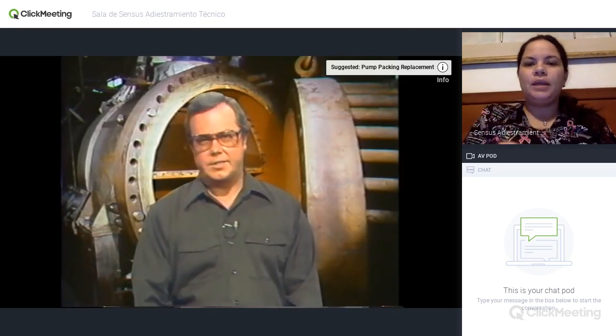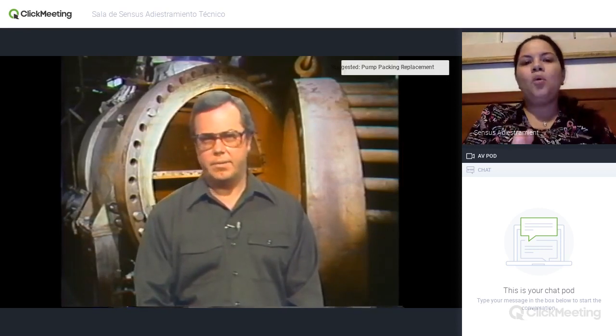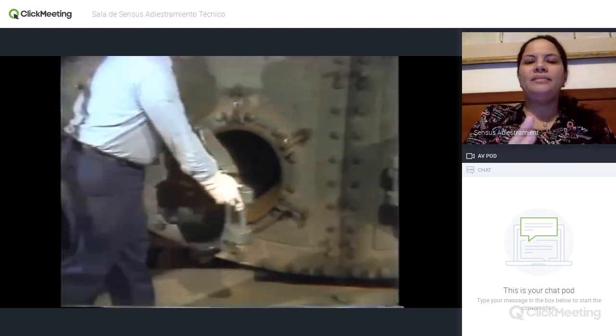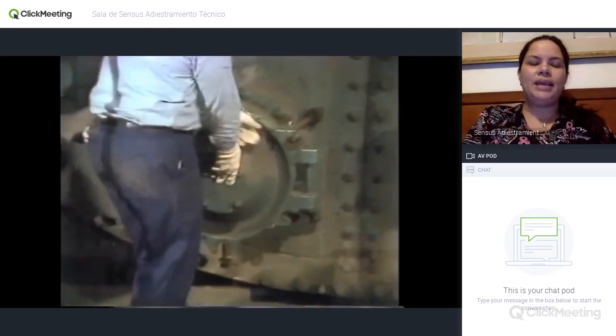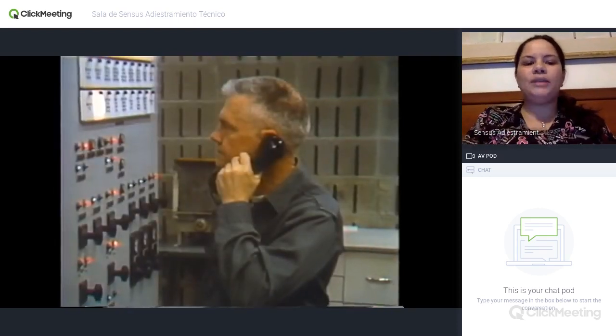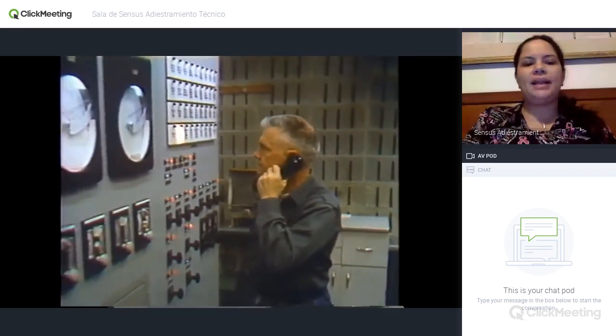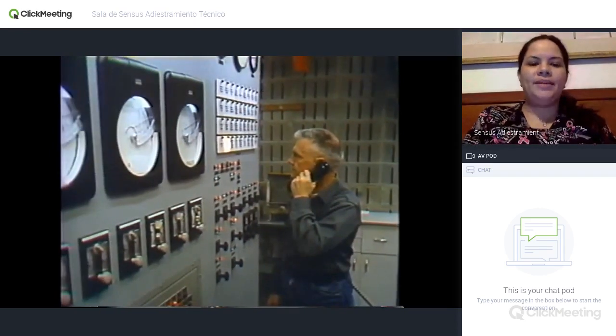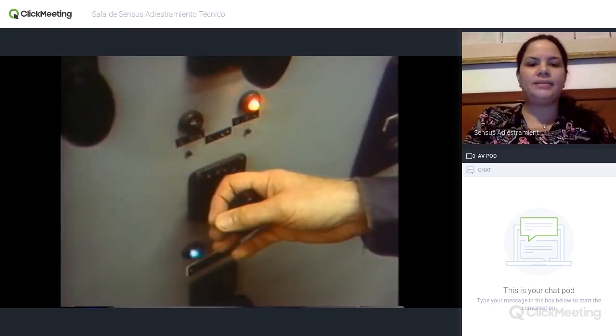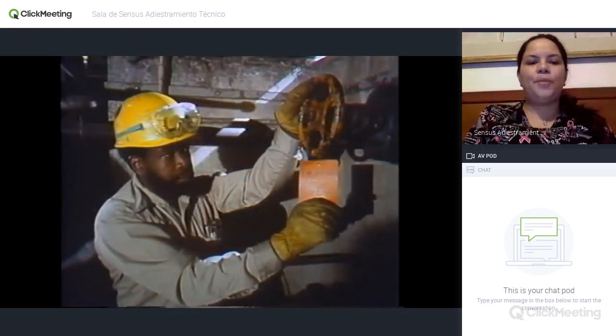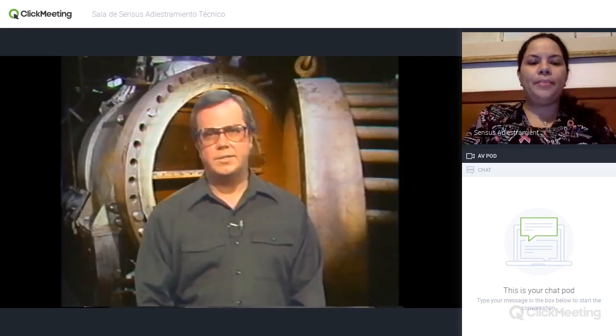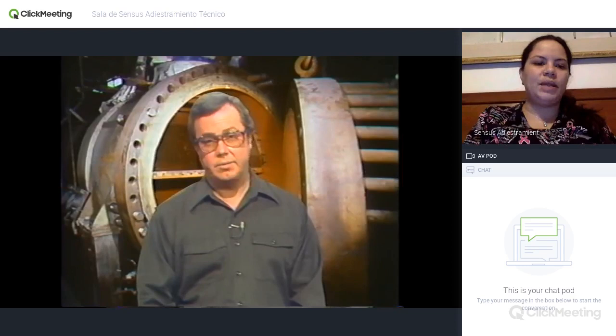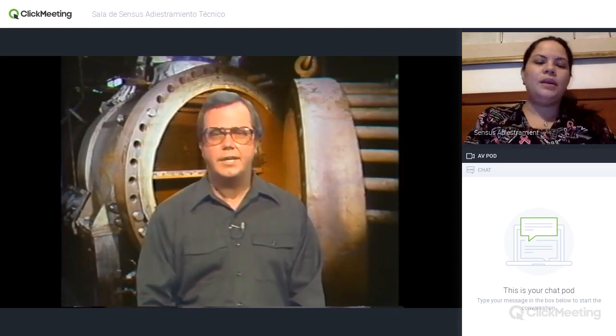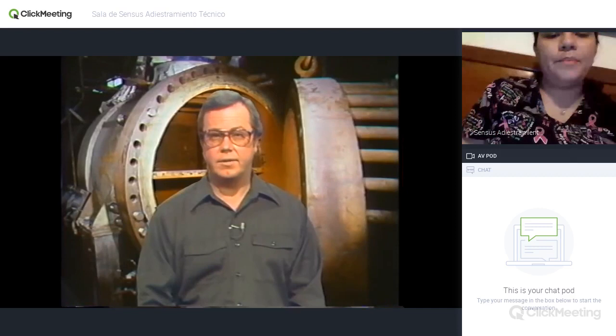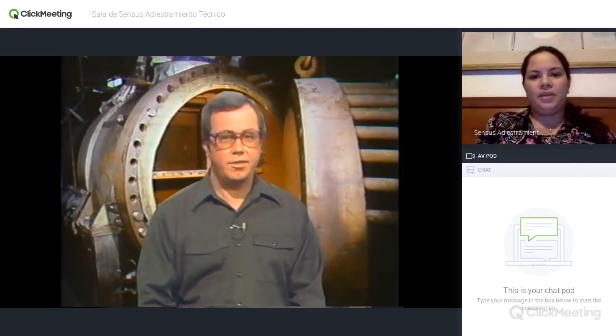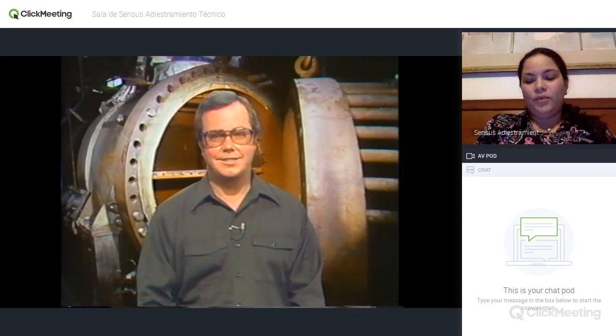After all the rest of your maintenance tasks are completed, it's time to clean up tools and equipment. When you've made sure that nothing's been overlooked, the unit can be closed up. It might be tested before it's put back into service. This might include flow testing, pressure or vacuum testing, leak tests, and so forth. It has to pass any tests that are performed before the component is ready to go back online. Routine maintenance tasks are usually pretty simple, about as simple as heat exchangers themselves. Still, each job has to be done with care and thoroughly completed. Then you can expect everything to work just fine when the system's put back into service.